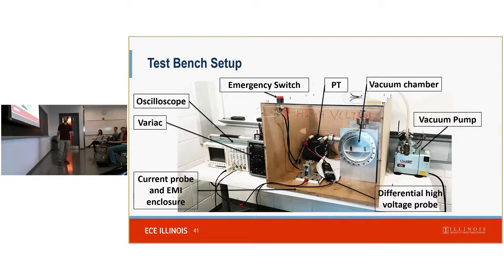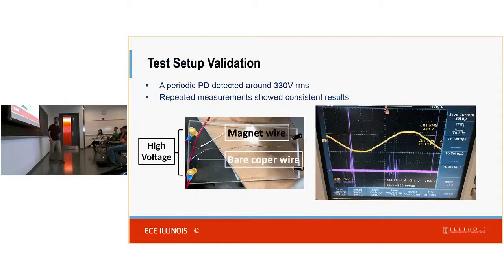Point out also that there's a vacuum chamber. So the insulation tends to be less effective at partially reduced pressures. And so by running it in a vacuum, we can simulate altitude, airplane altitude. That allows one more set of control for understanding the qualification of the insulation.